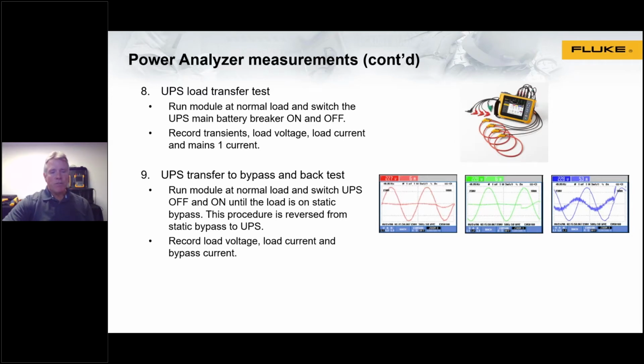Last test is transferring to bypass and back. What you would do is run at normal load, switch the UPS off and on until the load is on static bypass, and then again capture the same types of events: load voltage, current, and bypass current. And then when you go off of static bypass to go back to UPS, you would repeat the same test. So essentially, that's our pre-installation tests.